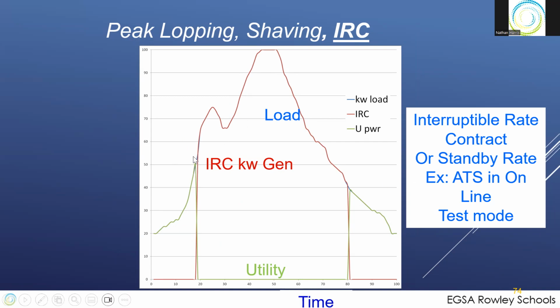You can't see the colors here very well, but at some point we got a signal from the utility, get off my grid, and you started your generators. They took over, the gens ran the whole load, and utility went to zero. And then at some time later in the day, it said, okay, now you can come back on again. And we synchronize back to utility and shut the generator off.